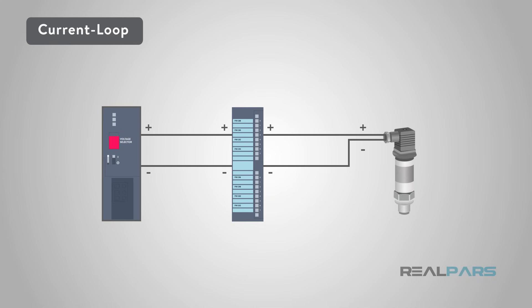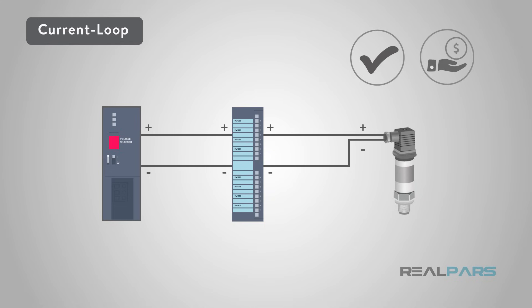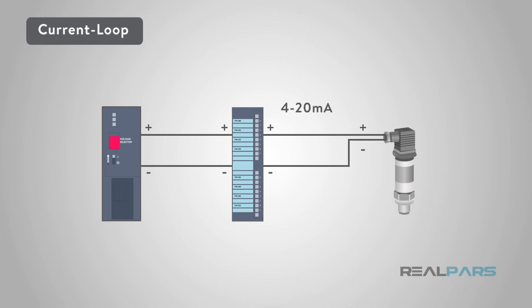Current loop data transmission is simple and cost-effective. Only a small amount of current, 4 to 20 milliamps to be exact, is required over a single pair of wires for each current loop sensor. One 2-amp, 24-volt DC power supply can drive dozens of sensors.